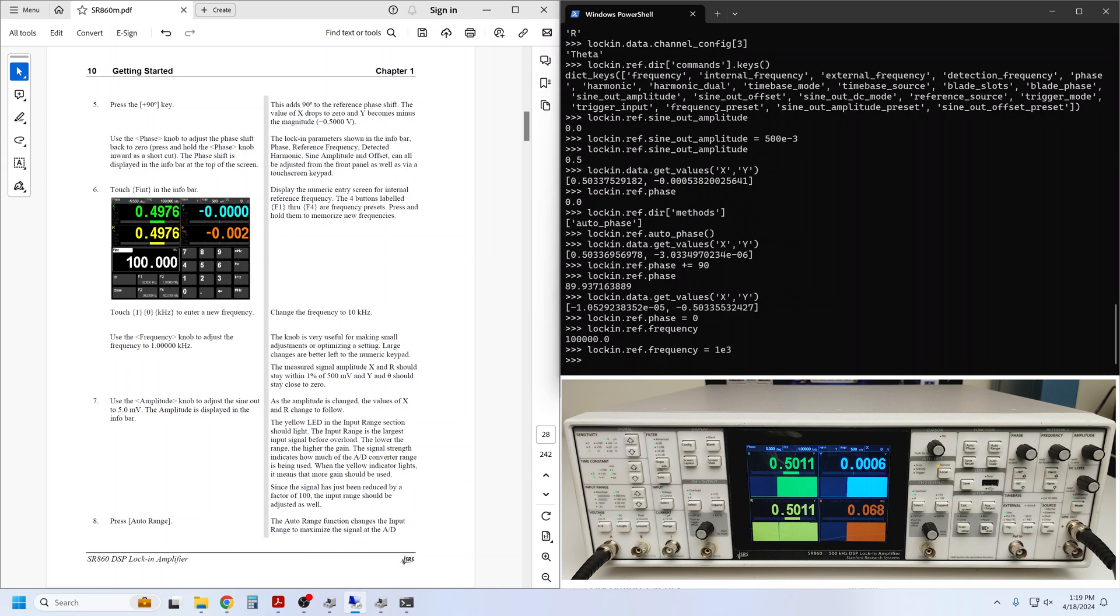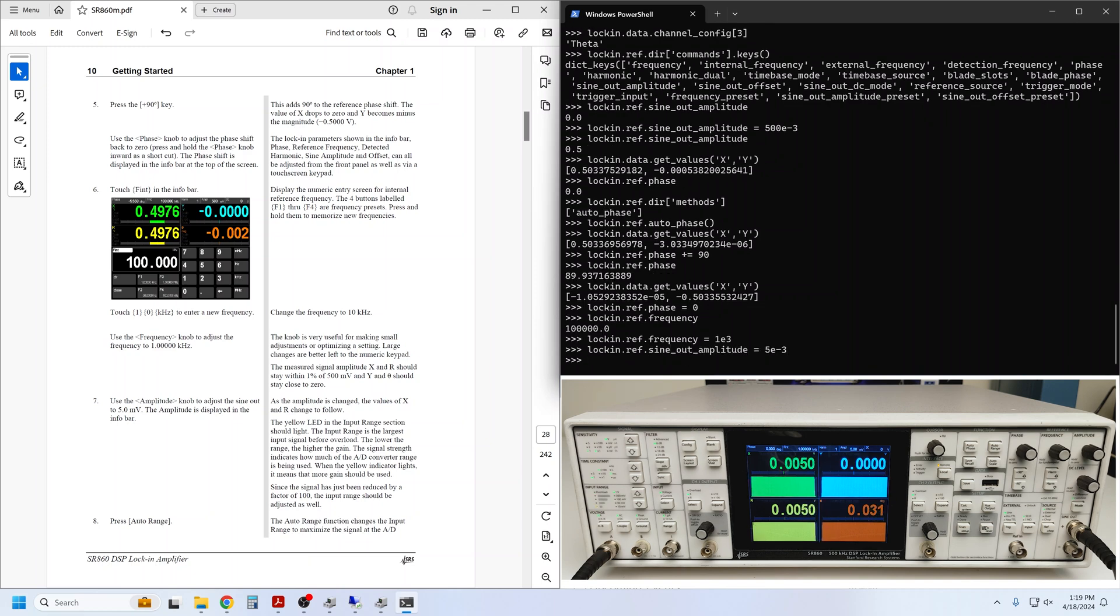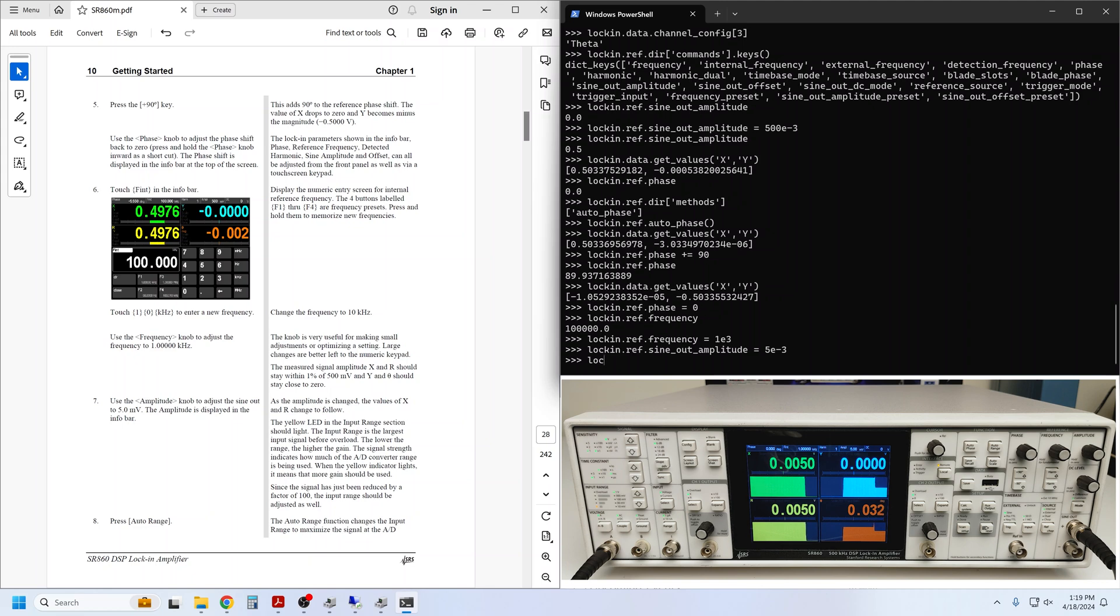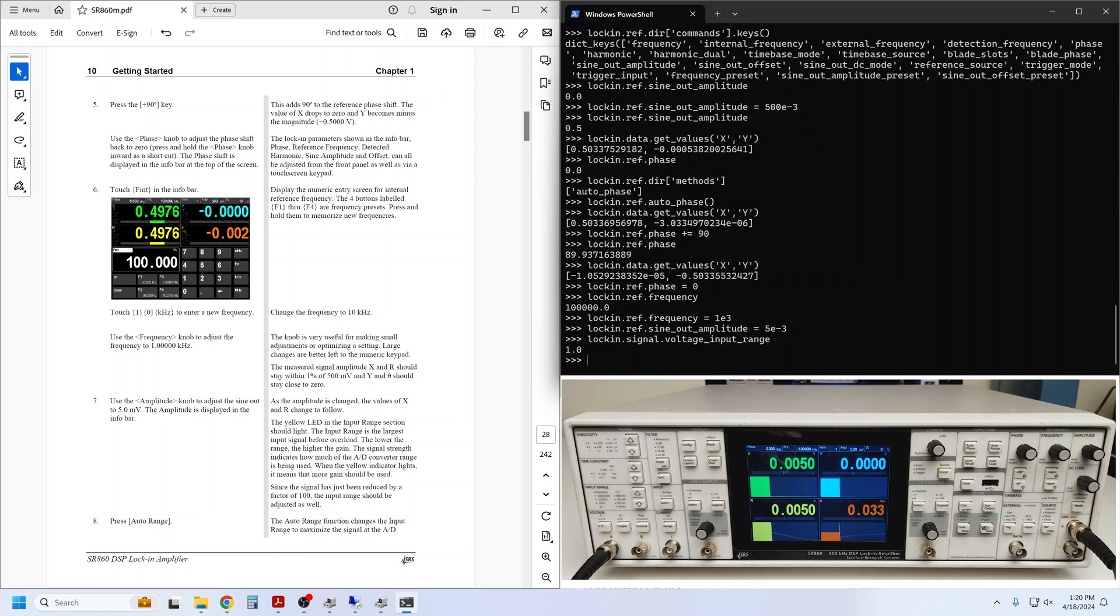Next, to understand the input range and signal overload behavior, we can make some adjustments to the signal amplitude. First, we set it to 5 millivolts. By default, the lock-in is configured to accept inputs as large as 1 volt. That setting lives in the signal component and is called voltage_input_range. Our 5 millivolt signal is a small fraction of this 1 volt range, so it makes sense to adjust the input range.